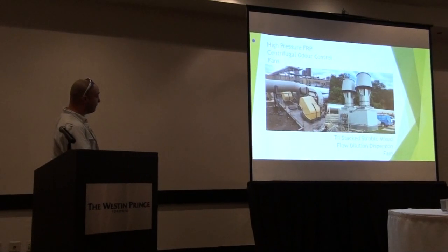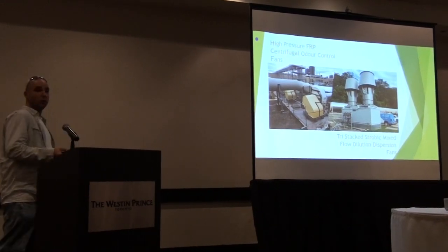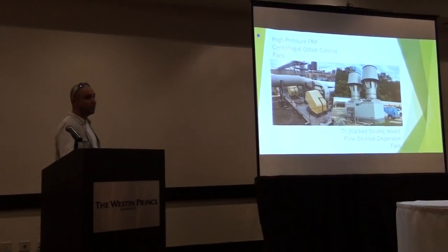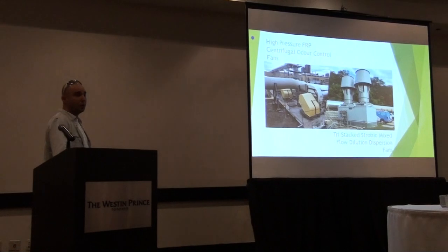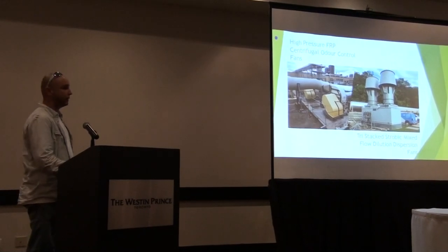Now you can see we have odor control fans — there are three, two of which are in use at a time with one on standby, so there's always redundancy, which is typical for the plant. The biggest units are 200 horsepower. The biggest issue surrounding these was the sound enclosures — they required redesign because they were too small and didn't leave room for maintenance access.